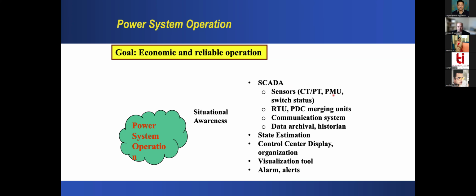So it might be a different system, but eventually it's also helping us bring data and control. Control is rare with PMU, but there are examples where PMU is used for control. Switch status is another example of a sensor. Then we have a remote terminal unit, a PDC merging unit which brings data from PMU as a PDC, a communication system, and data archival historian—all part of SCADA. Then we have software in the control room, like state estimation, control center display, visualization tools, and alarms and alerts.